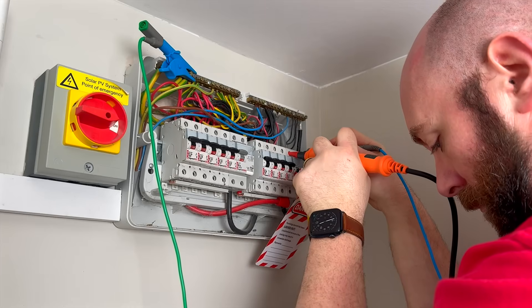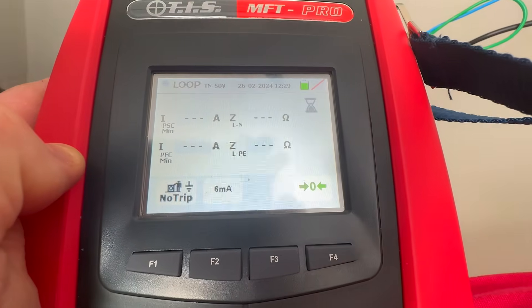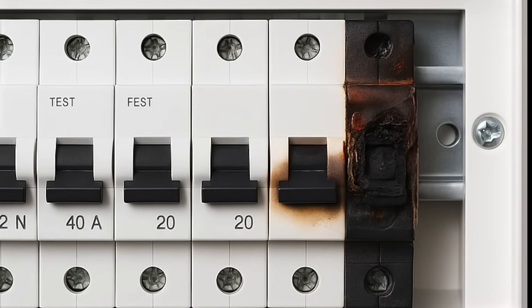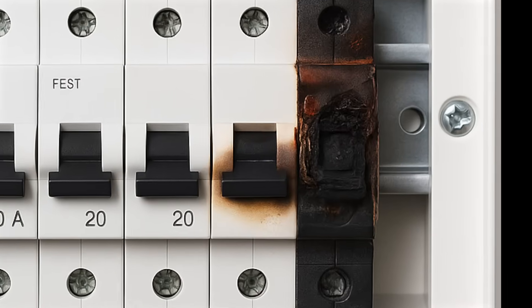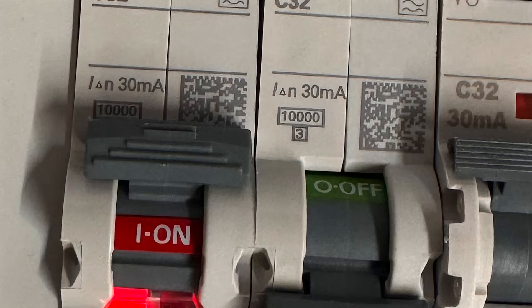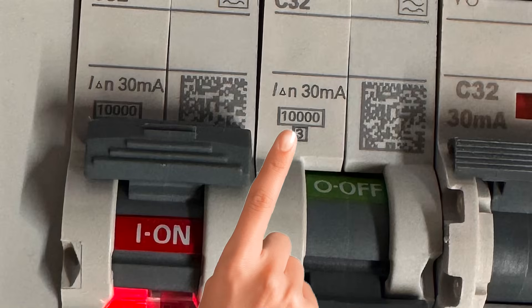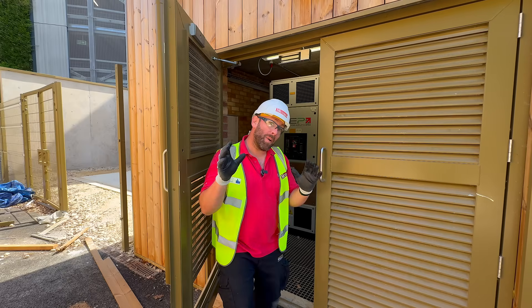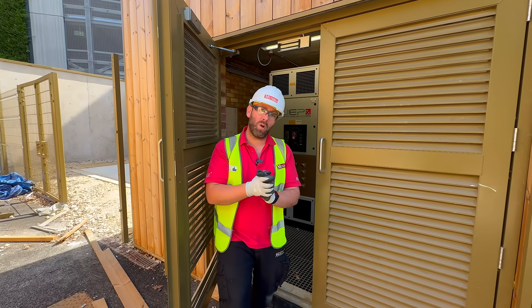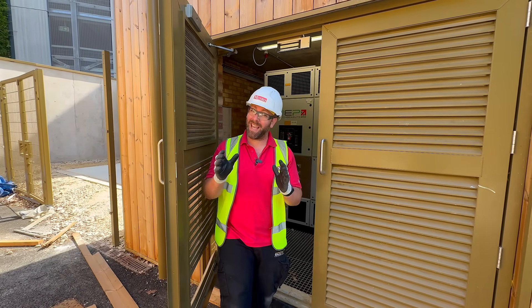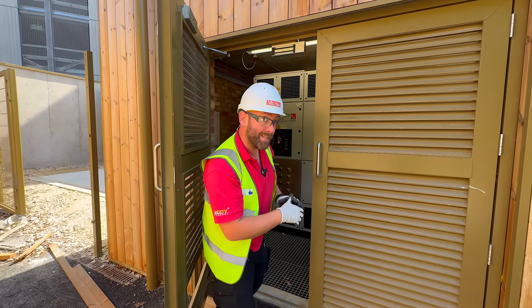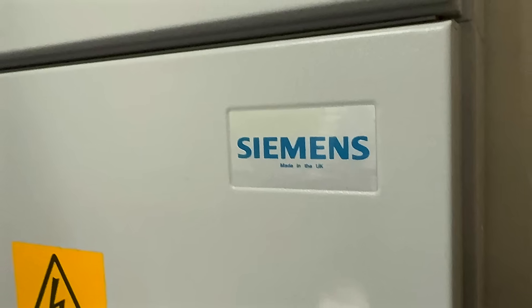If the prospective fault current is higher than what the device is rated for, it might not trip safely. In fact, it could overheat, get damaged, or even catch fire. So it's crucial that the breaking capacity of the protective device exceeds the prospective fault current. In a place like this, where the substation is close by, the prospective fault current could be much higher than the 6KA rated on a lot of protective devices. And this is where Siemens have really stepped up — their AFDD is rated to 10KA.